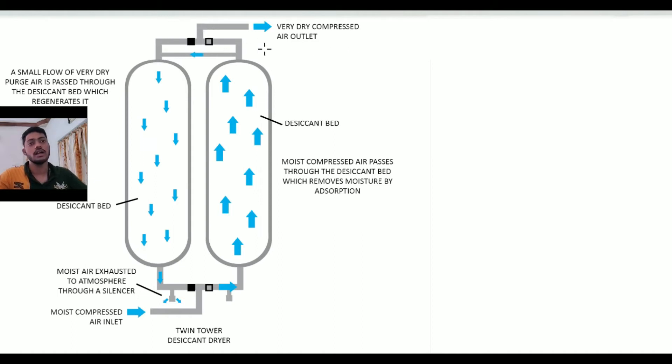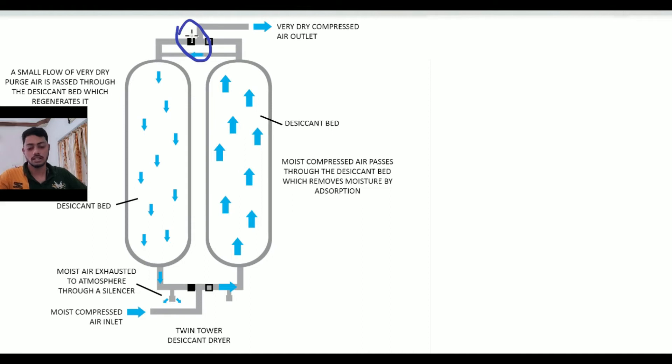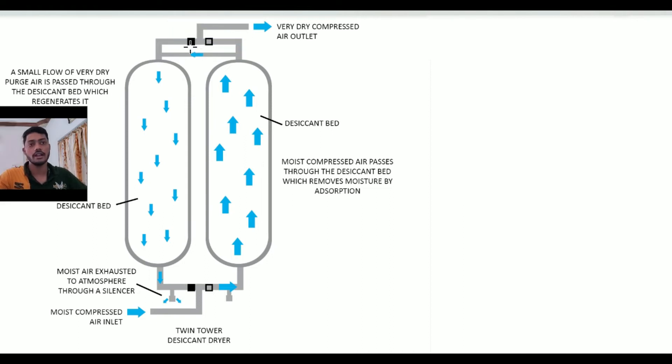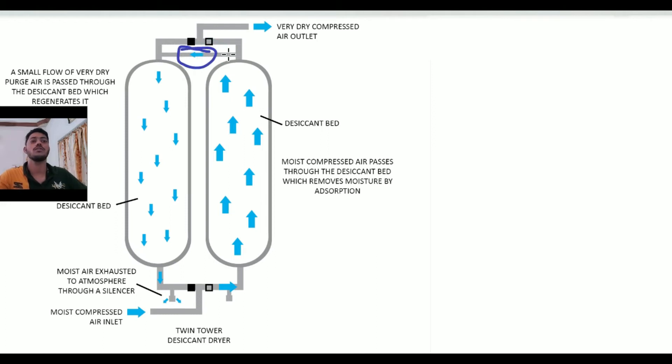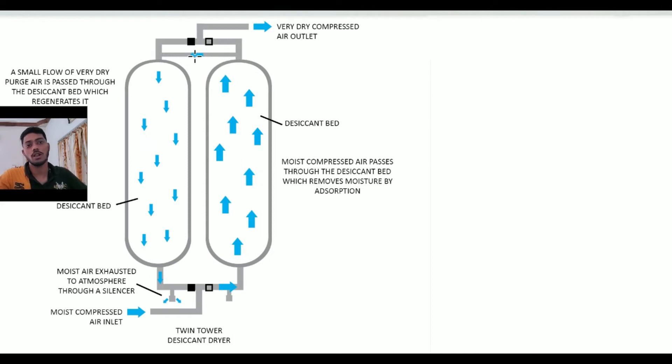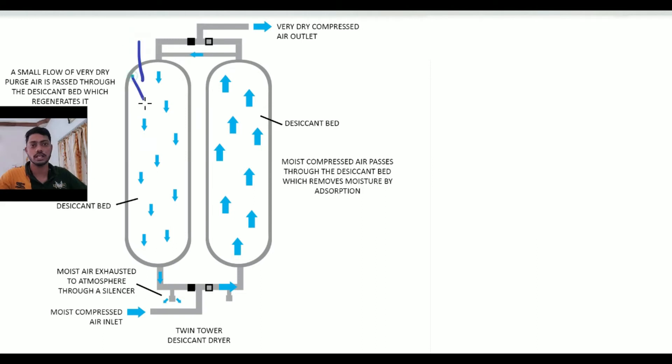The very dry compressed air is the outlet we get. You can see here this valve is closed, so the dryer is not moving this side. You can also see one small orifice line which flows a small amount of air towards this offline cylinder or regenerative cylinder.